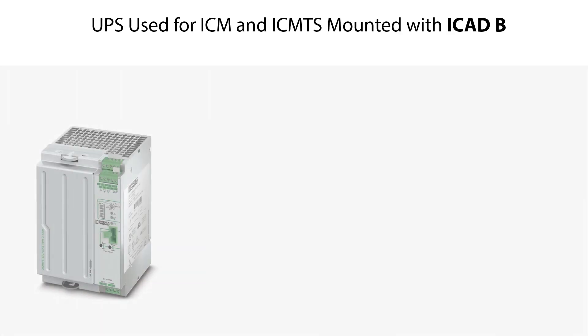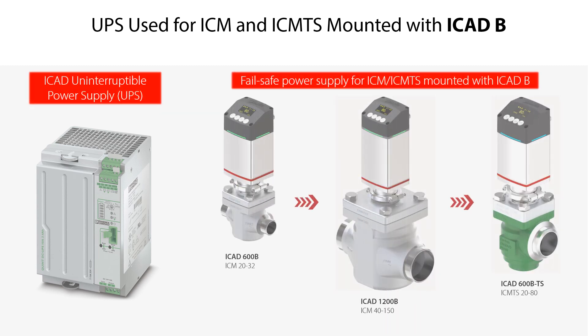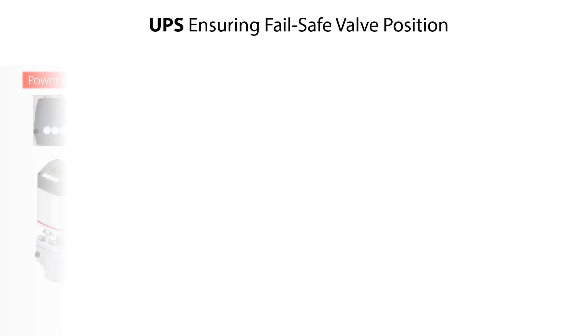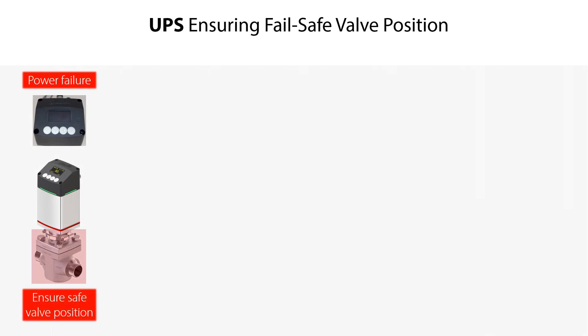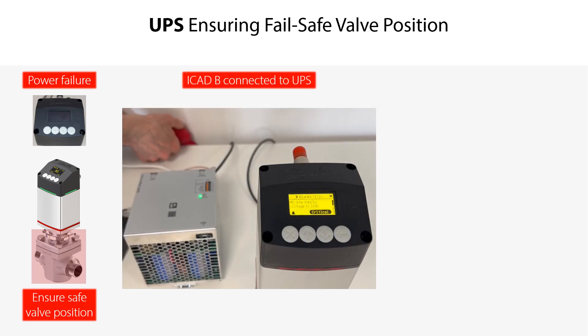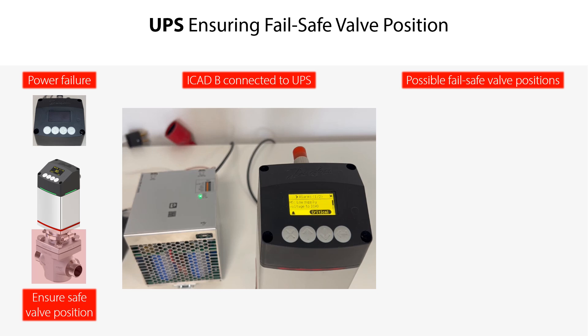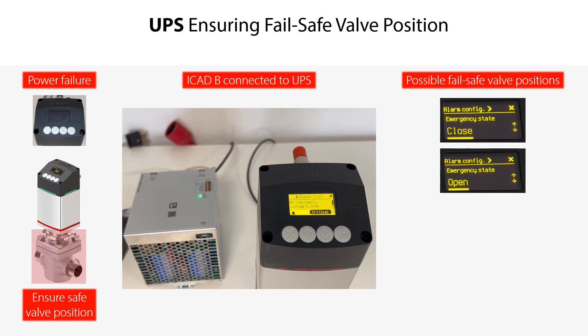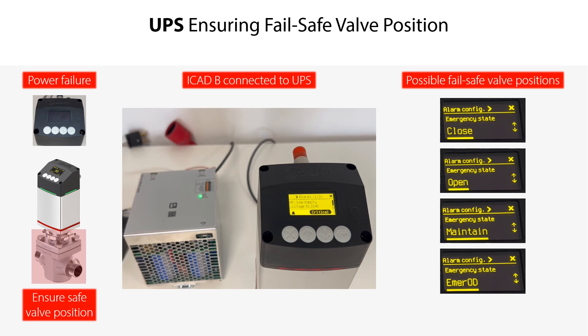Here you see an example of the Danfoss ICAD Uninterruptible Power Supply, or simply called UPS. This UPS is designed to be used as a fail-safe power supply for the ICAD-B mounted on ICM and ICM-TS motor operated valves. In the event of power failure, there is a need to ensure that the ICM and ICM-TS valves enter a safe valve position. Once the ICAD-B is connected to the UPS, during power failure this fail-safe solution will give the following possible valve positions: the ICM and ICM-TS closes, opens, maintains current position, or enters a specific valve opening degree. The actual valve position depends on how the UPS is configured in the ICAD-B.